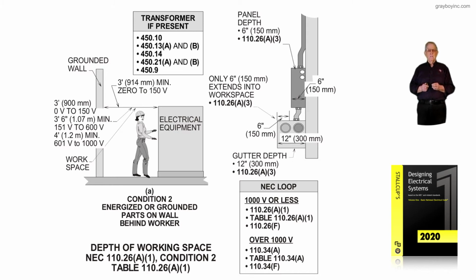And then for 450.9, it does not matter where we install that transformer, we must install it in such a manner that ventilation can be provided that will carry off the heat of the transformer as we load it up and dissipate the heat away from the transformer windings. Now, that's the main thing about the 5 bullets that you see under the title head, Transformer if present. Now, if we're dealing with arc flash conditions, then we know 110.16 requires a label to warn the electrical worker that an arc flash condition could be present inside this equipment when it's energized.